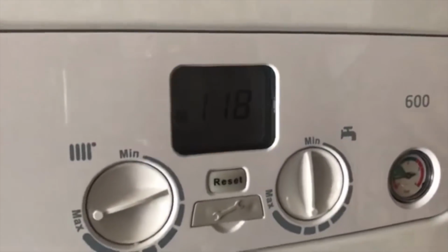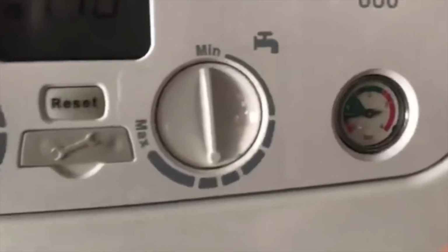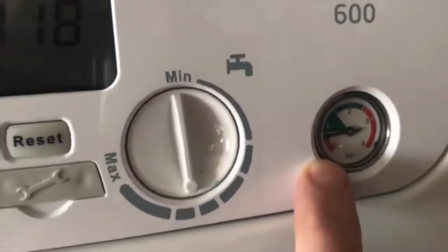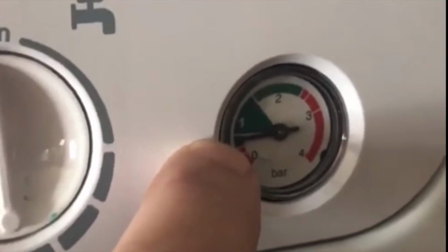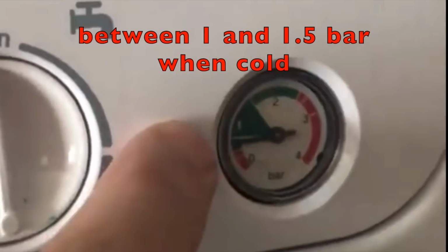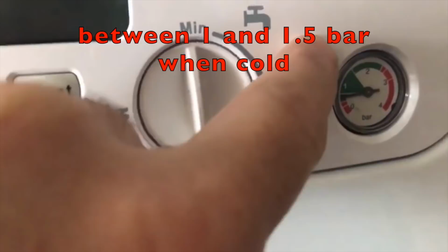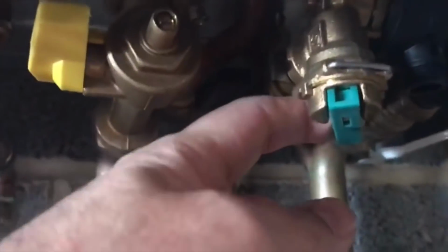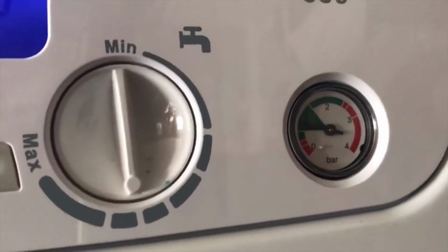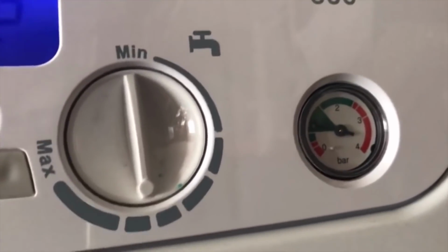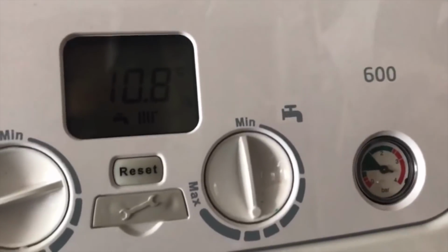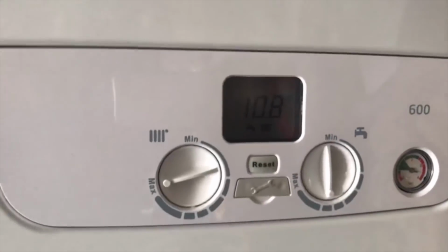Now if you get a flashing blue light with a 118 error code, it probably means your water pressure is low, so we need to keep the water above the 1 in this green section. All we need to do is go under the boiler, pull this little green lever down, and it'll allow water into the system. While you're watching the gauge and the water coming up into the green section, once the blue light goes out, the boiler will reset itself and it's ready to go for heating and hot water. So that's how you top up this Baxi 600.